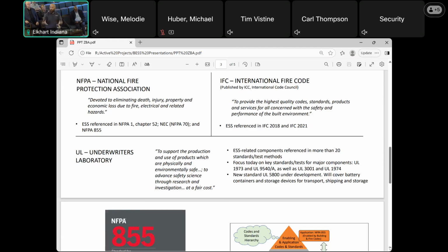So when we look at the propagation test, as he alluded to earlier, there are different safety mechanisms integrated into place. Under UL 9540A, we don't put those safety mechanisms in. We actually have to take all those safety mechanisms out, charge the batteries up, and then fail them. Because again, we want to see what that failure looks like if all the safety mechanisms are not integrated and secured in place. Does that make sense so far for everybody?